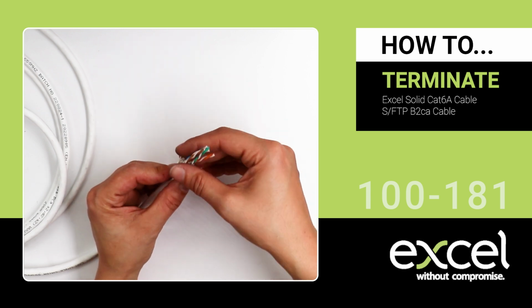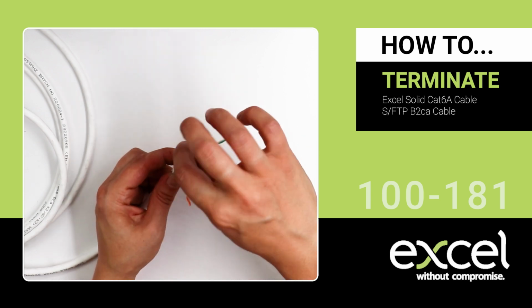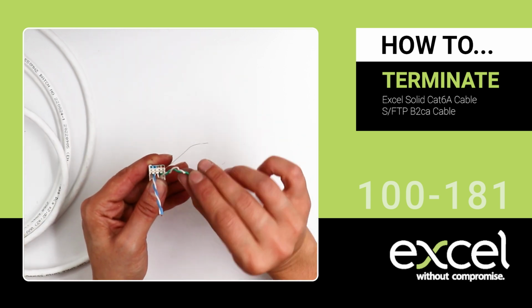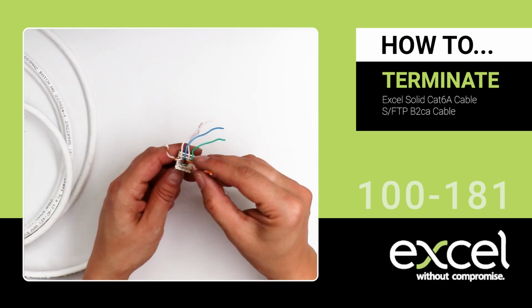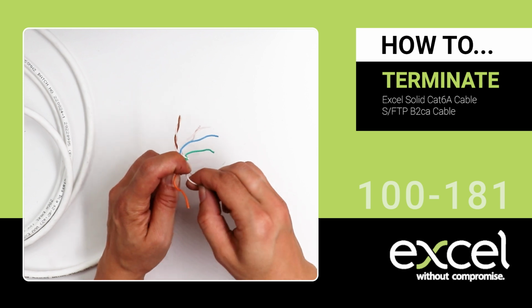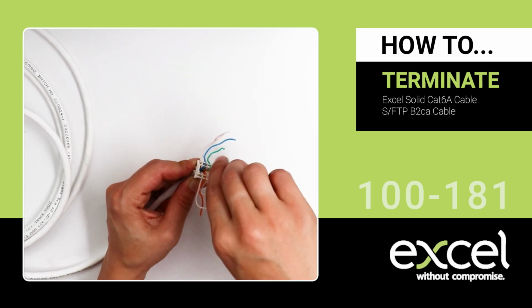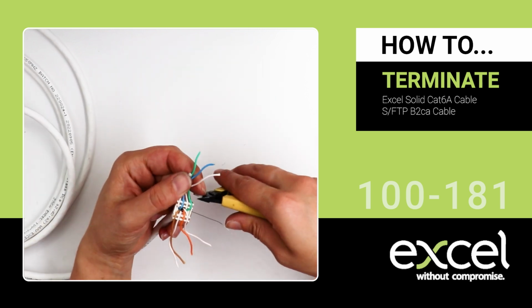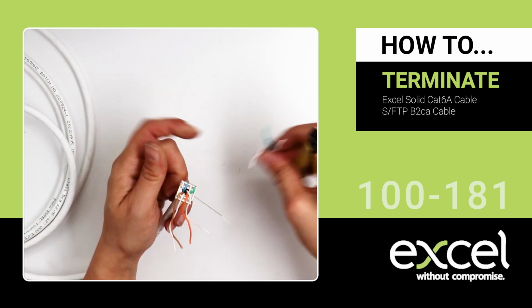Insert the cable through the termination cap, then untwist and fan out the pairs. Following the colour code on the cap, insert the wires into their designated slots. Double check that the wires are in the correct position, then trim the excess.